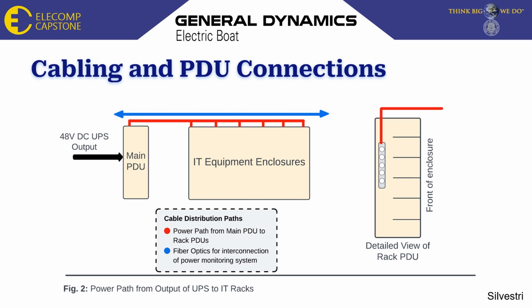That is going to distribute power to a rack PDU in each rack. These rack PDUs are essentially switched, meaning we have the remote ability to turn on and off individual outlets, as well as receive data on what's going on in each outlet, such as power draw, current levels, and the capability to see any type of fluctuation going on.